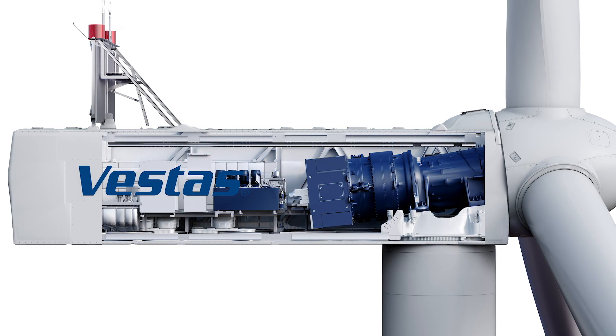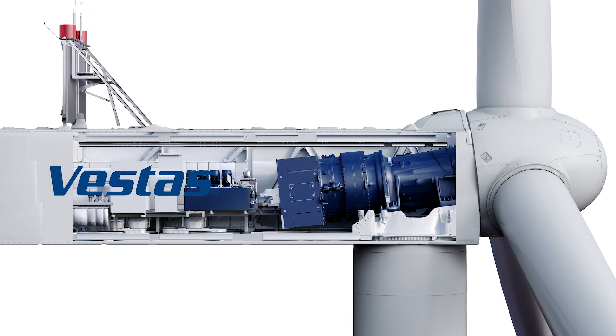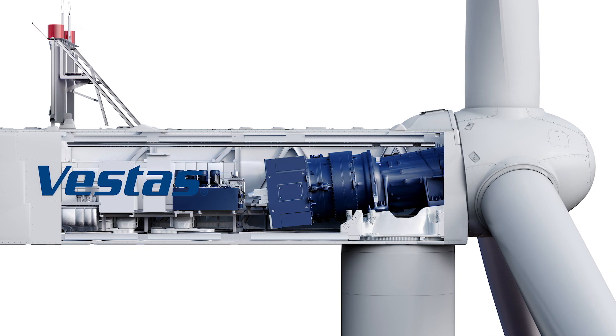Vestas have also taken an interesting angle to the use of rare earth magnets in their drivetrain. Not only a cheaper magnet, but also one that has a greater security of supply. The wind industry has come unstuck with magnetic technology and rare earths before, and I think that's pretty clever. They've had to do quite a lot of work to make neodymium work rather than dysprosium, especially in the cooling of the generator, but it does look like they've got that sorted.